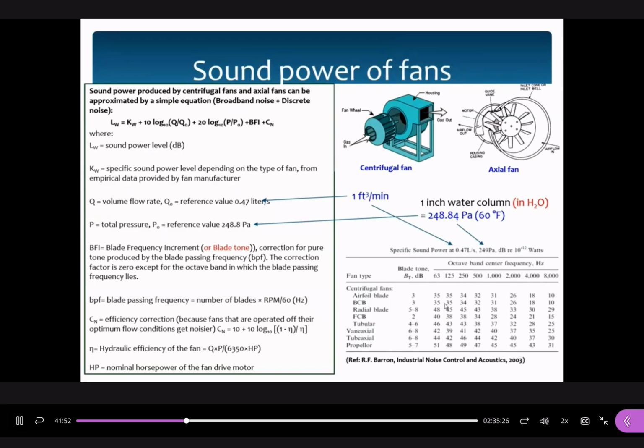This is just for your information, to explain why we take these two figures as references. So Q is the volume flow rate and P is the total pressure; BFI is the blade frequency increment or blade tone, and Cn is the efficiency correction — we use these equations to find the efficiency corrections and the hydraulic efficiency of the fan. You can follow all these equations, including horsepower, where 1 horsepower equals 746 watts — just for your information.